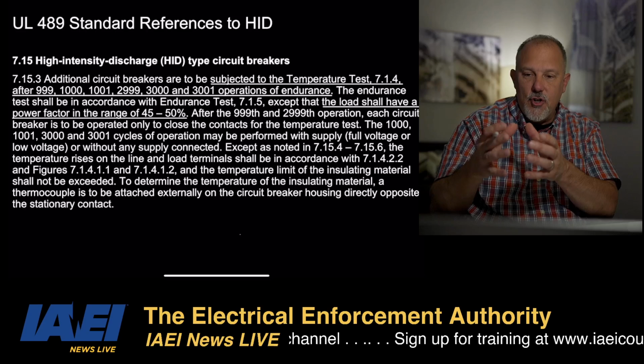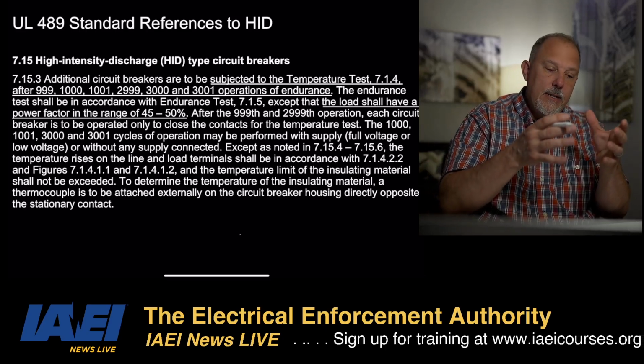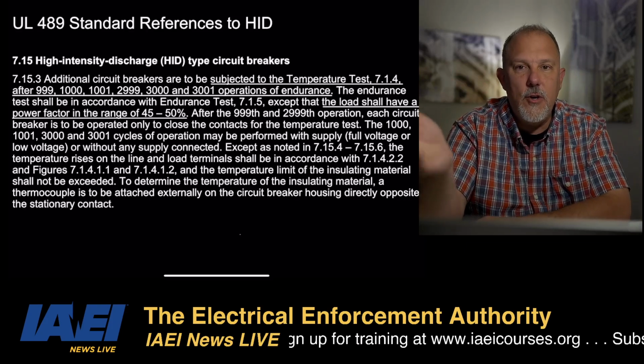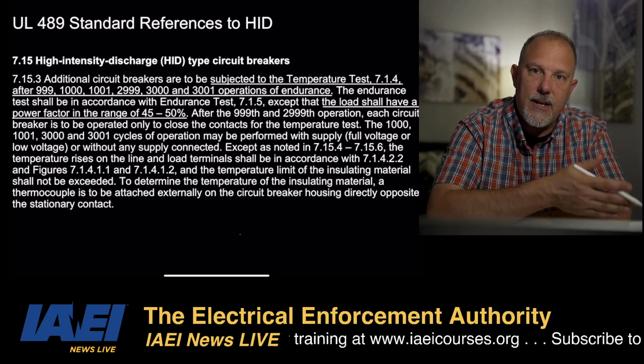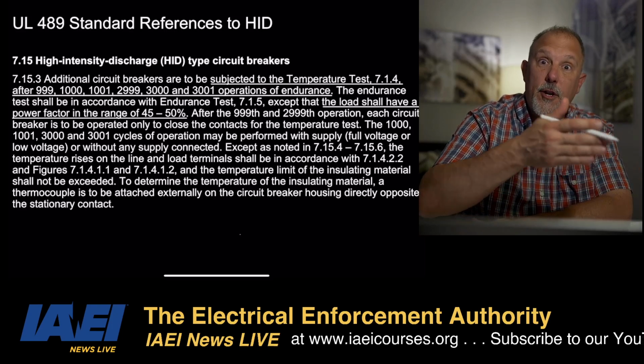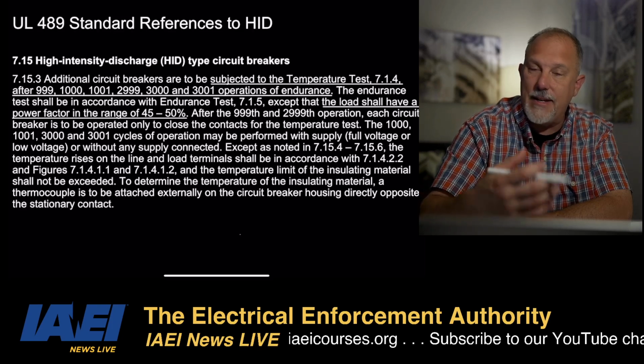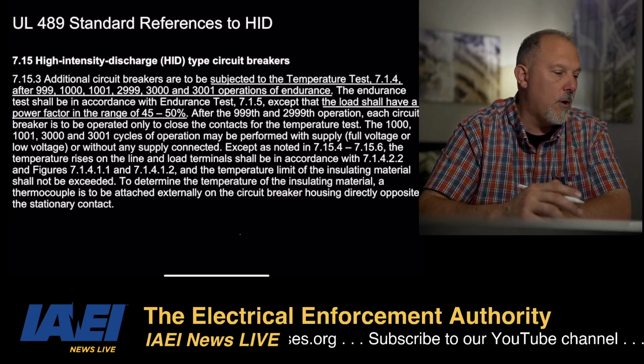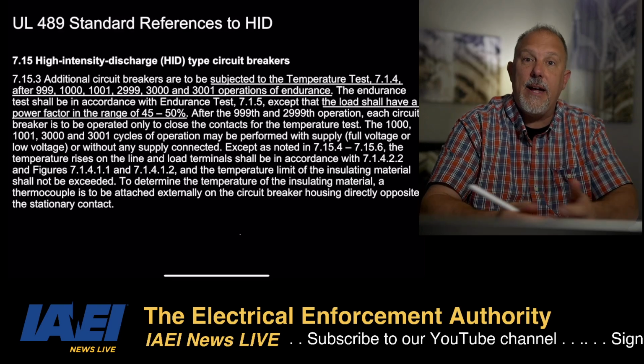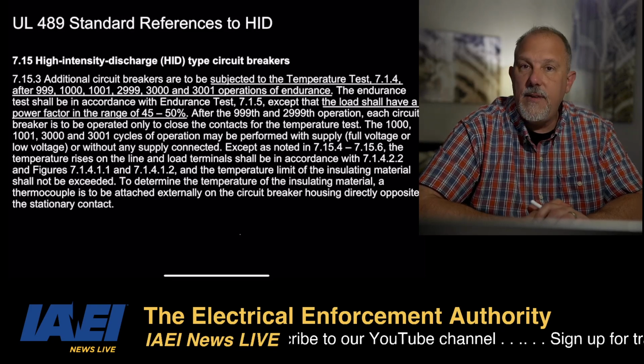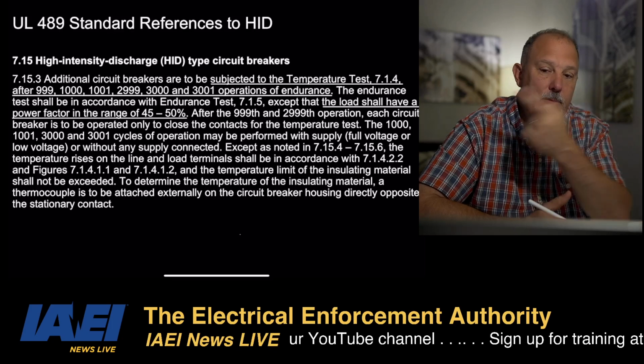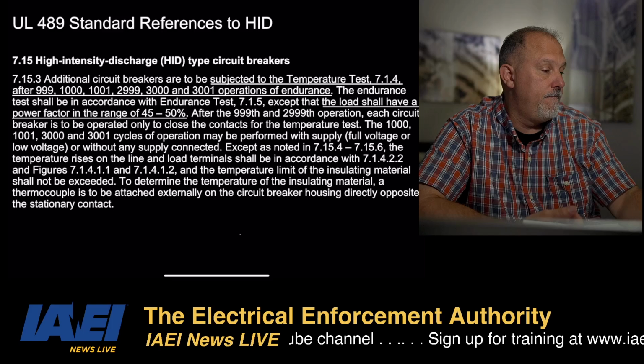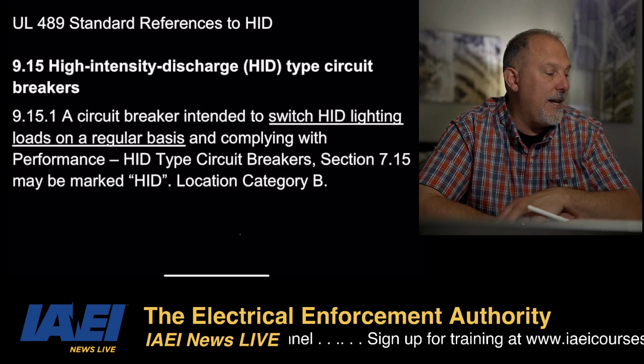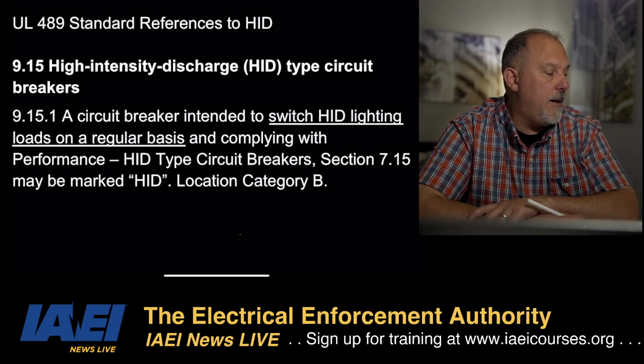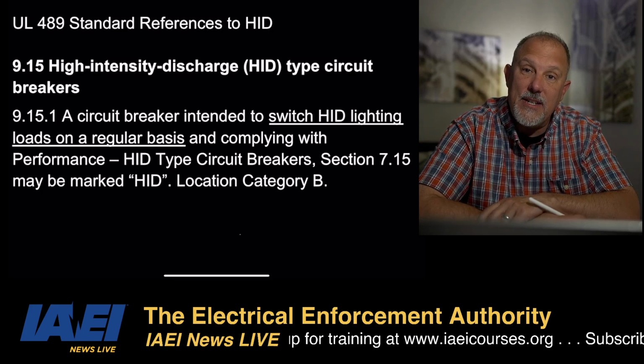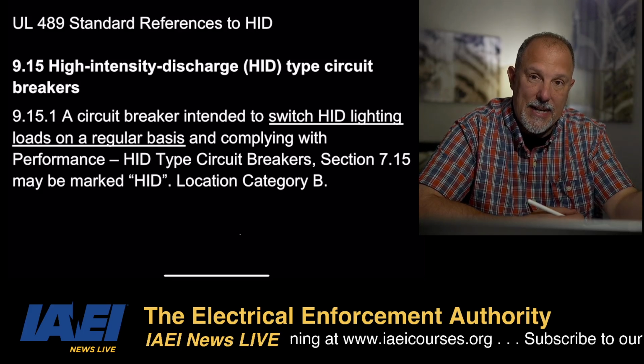Remember, when I have a good idea of what the load is, if I'm going to design tests for a specific load, if I know the characteristics of the load, I subject the device to those characteristics over and over and over from an endurance perspective, and that gives me a better flavor for whether or not that product is going to survive. And if I'm the design engineer and I know I'm going to be receiving these harsh tests, I may have to change my design to meet these performance requirements. A circuit breaker intended to switch HID lighting loads on a regular basis and complying with performance requirements may be marked HID in location B. So it tells you the performance test requirements that you need to pass and the marking requirements.